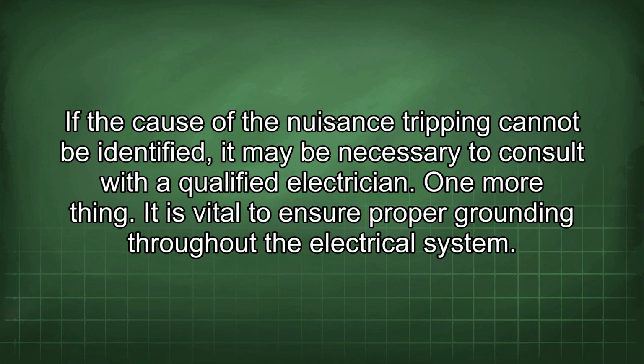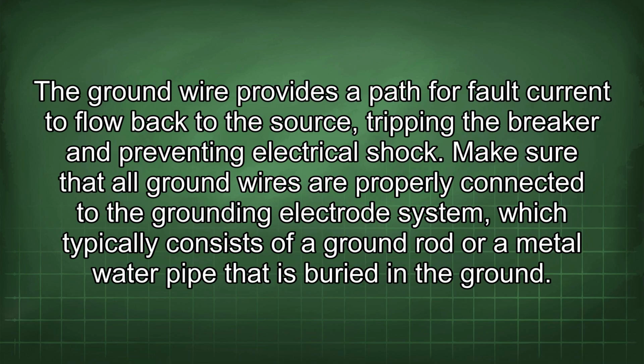One more thing. It is vital to ensure proper grounding throughout the electrical system. The ground wire provides a path for fault current to flow back to the source, tripping the breaker and preventing electrical shock. Make sure that all ground wires are properly connected to the grounding electrode system, which typically consists of a ground rod or a metal water pipe that is buried in the ground.